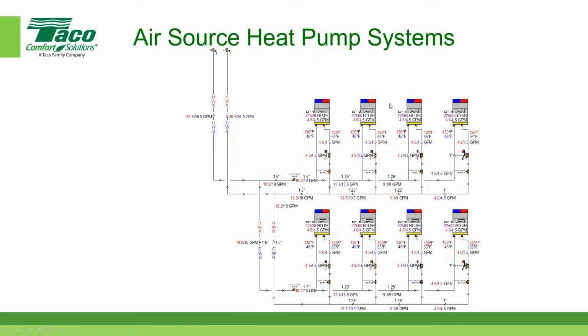And these are the terminal devices. And again, look at the entering water temperature, 130 degrees entering, 120 degrees leaving. And the GPM is 36.5. You can see it over here on the left, 36.5 gallons per minute. Whenever you do these systems, by the way, you always pick the higher GPM. So this particular calculation calculated the GPM for the cooling to be 35.9 and the heating to be 36.5. But in the real world, we would just stick with one GPM for this type of system, which would be 36.5 GPM. And this gives you an idea of what the indoor units look like.